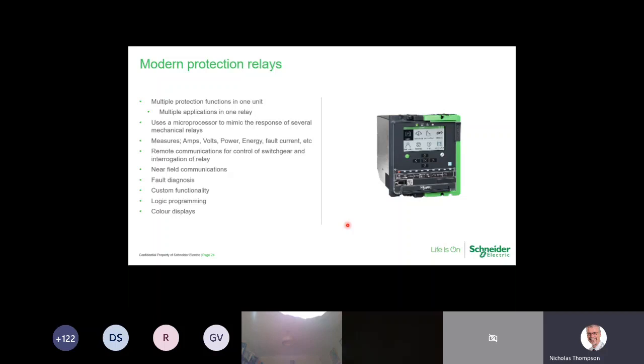They are working on really accurate CTs. The accuracy of protection CTs is quite low because the CT has got to work on a very, very wide current range from normal through to fault current, whereas a metering CT only needs to work on its normal current range from, say, 10% above normal, what would be classed as your normal load current, down to, say, 80% of its load, and you would have really accurate measurements.